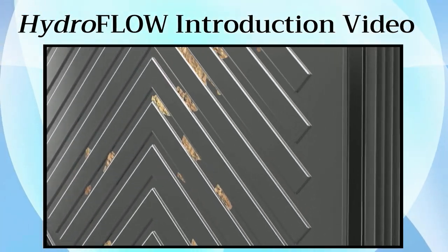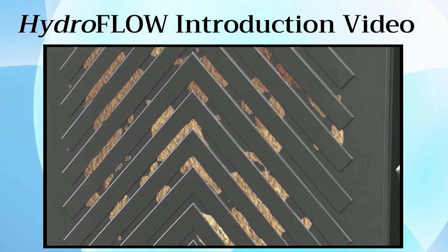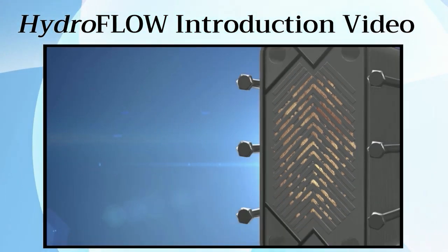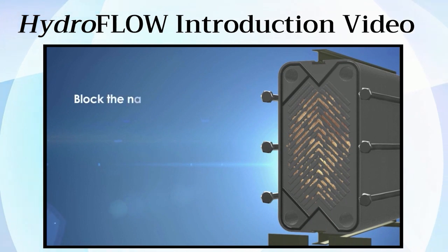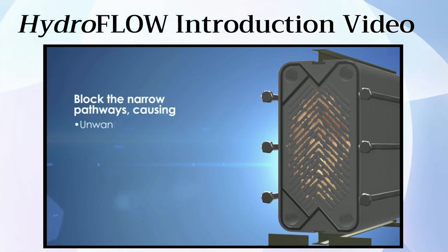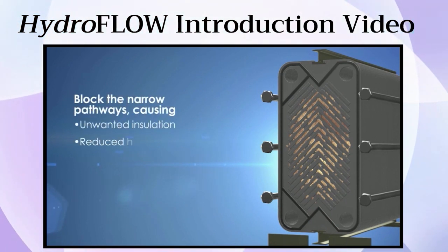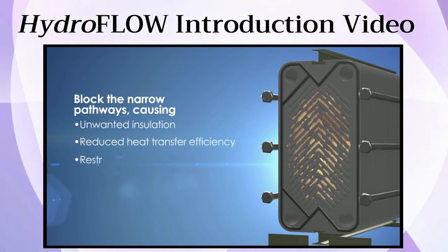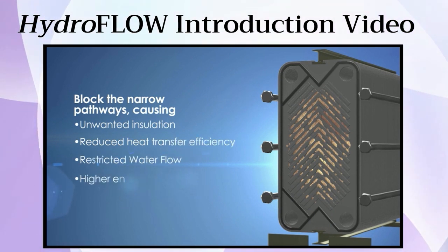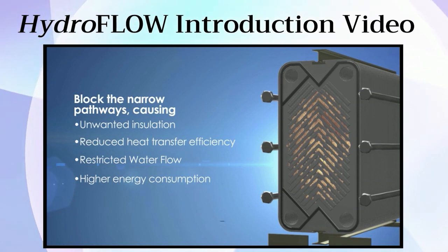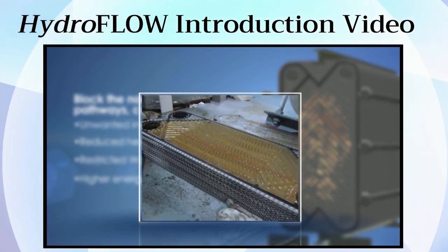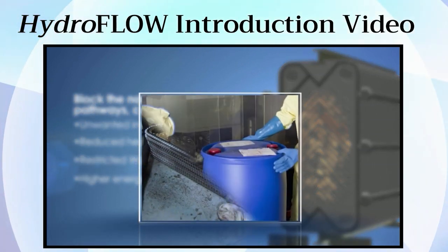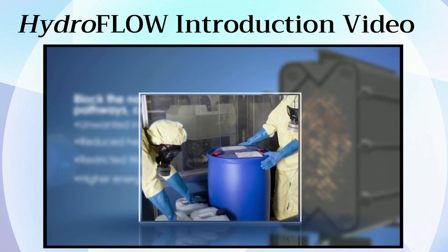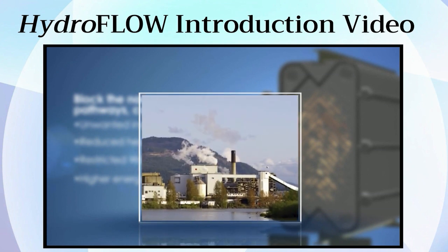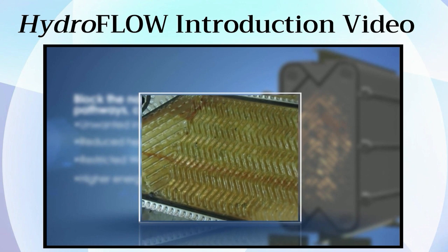Over time, accumulated scale, along with biofilm that consists of the bacteria and algae from the processed liquid, block the narrow pathways, causing unwanted insulation, reduced heat transfer efficiency, restricted water flow, and higher energy consumption. Eventually, systems need to be opened and cleaned. The process of cleaning the plates requires the use of hazardous chemicals, is time-consuming, and might cause damage to the equipment.